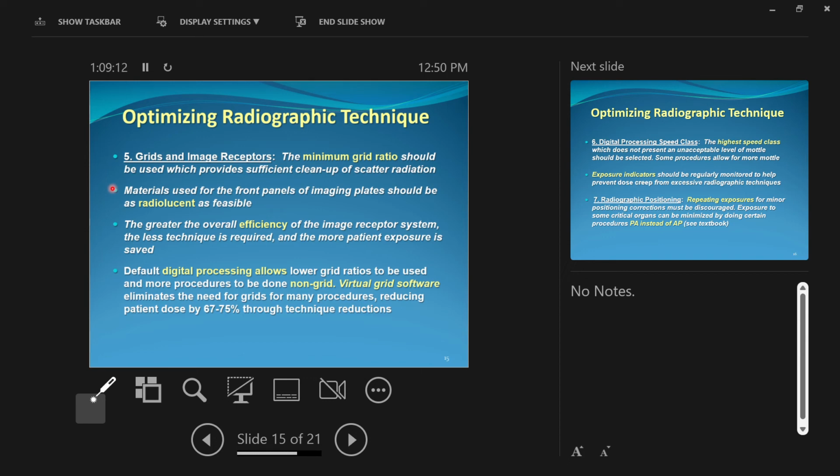Okay, and then this tabletop, right? This is an X-ray table. Underneath this table is a tray with an X-ray cassette, right? You could have an X-ray machine up here, and those X-rays would pass through the patient, through the table surface, and then hit this cassette. Okay, we want the front face of this cassette to not absorb X-rays. Okay, that way the X-rays can get to.